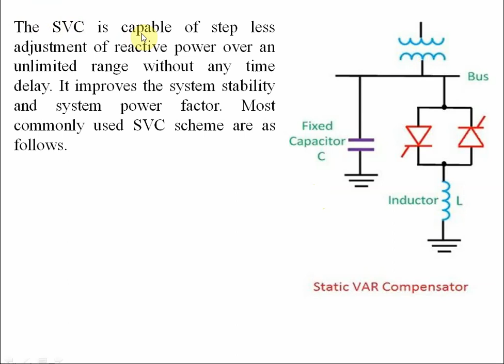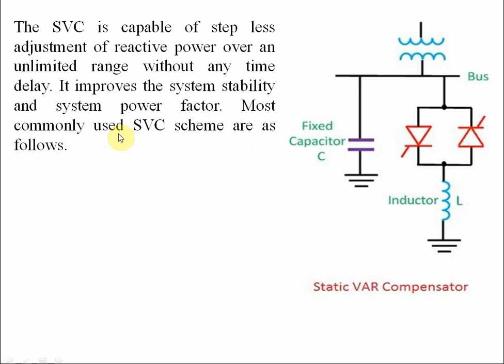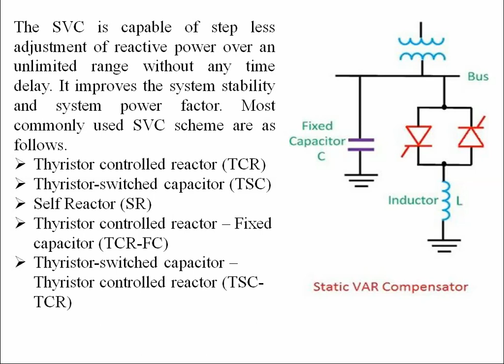This SVC is capable of stepless adjustment of reactive power over an unlimited range without any time delay. So this is one of the advantages. You can say it improves the system stability and system power factor. And the most commonly used SVC schemes are the thyristor controlled reactor (TCR), thyristor switched capacitor (TSC), self reactor, thyristor controlled reactor with fixed capacitor, and thyristor switched capacitor with thyristor controlled reactor, TSC-TCR.